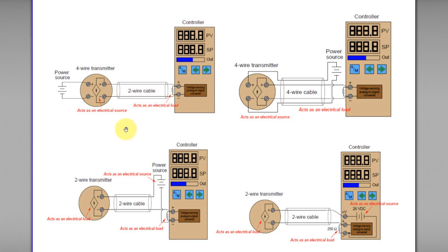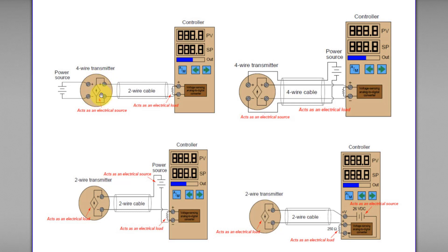As I mentioned earlier, a circuit should have a minimum of one power source and one load. So this transmitter needs to act as an electrical source. Here we use a four-wire transmitter. What is the difference between a four-wire transmitter and a two-wire transmitter? A four-wire transmitter has four wires: two wires connect to an external power source to power up the transmitter, and another two wires are used for signal communication in the loop. So this external power source powers the transmitter, and the transmitter output terminal is used for signal communication between the transmitter and the controller. So this transmitter acts as an electrical source.